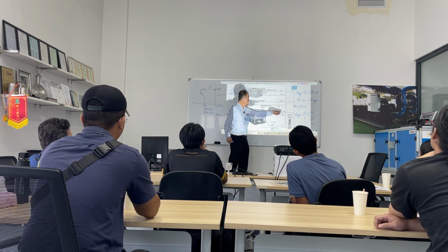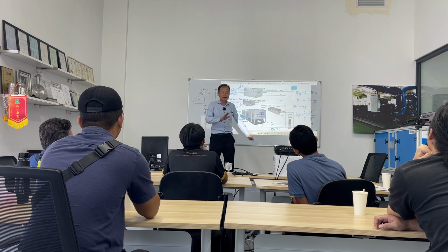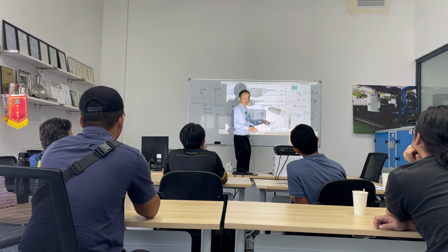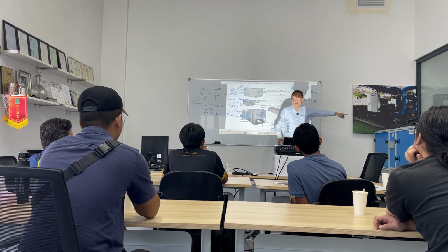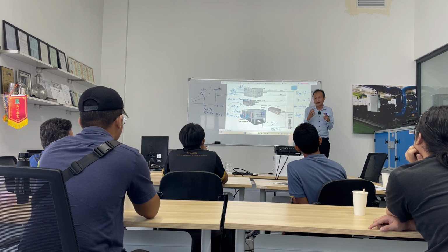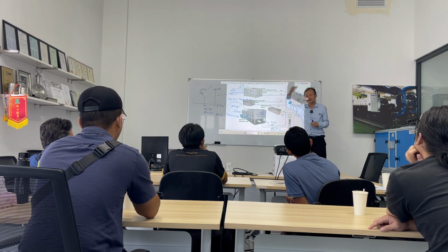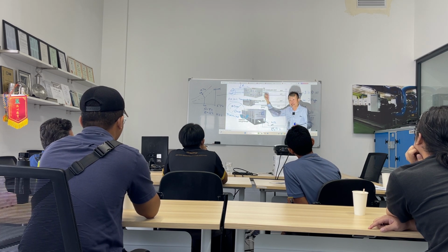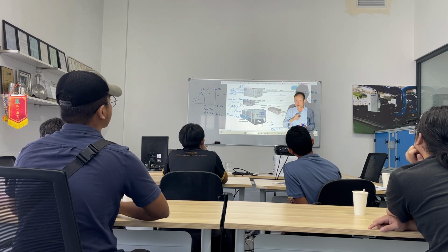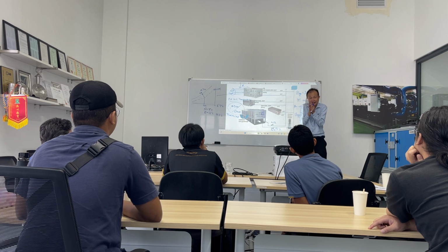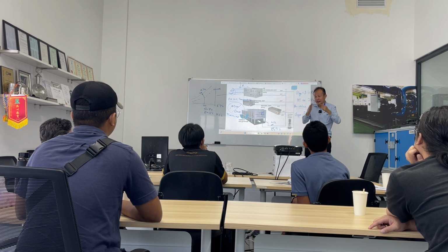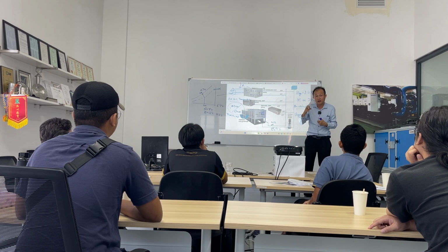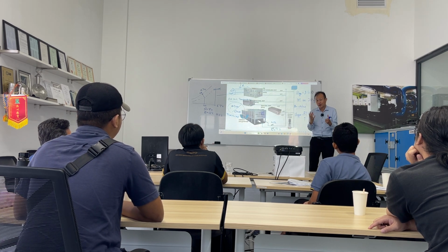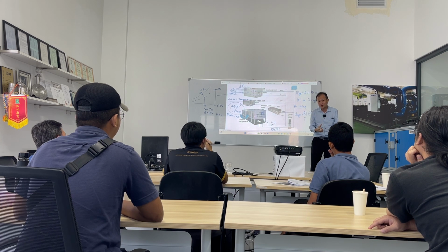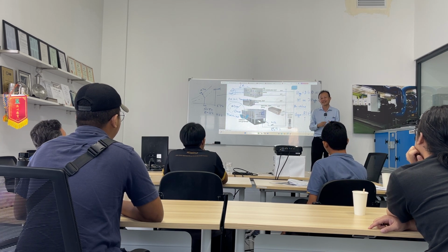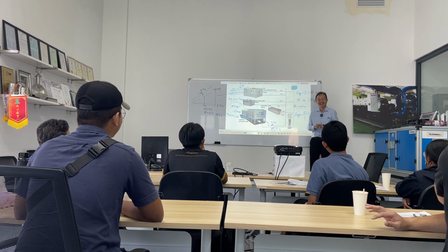This lower temperature goes to the AHU. Before I ask you this question, why do I want to design lower temperature? Then at the AHU, the cooling coil is colder, right? Then I can design a lower air temperature coming out from the coil. When I do this, I can also increase the air temperature difference. When I increase the temperature difference, the airflow I can also design lower. When I design lower, your fan is smaller, fan motor smaller, duct smaller also. Very happy also, right?